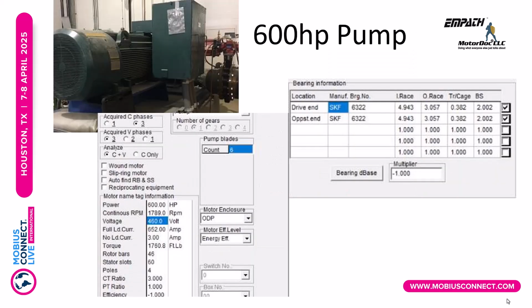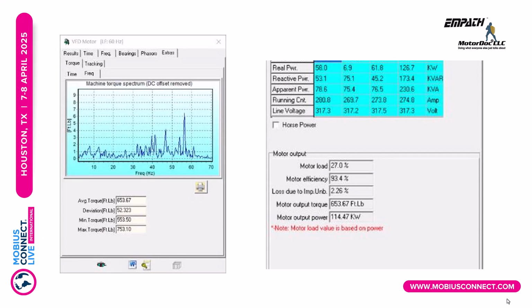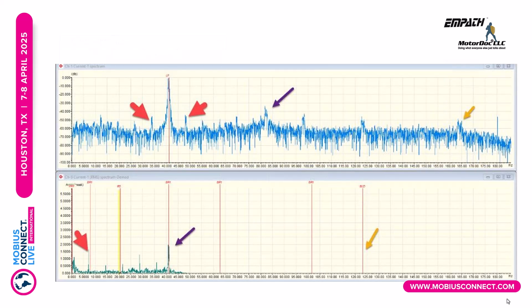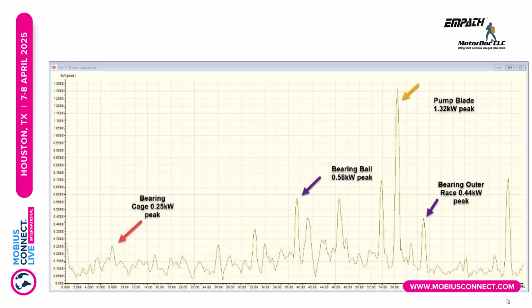This one here, 300 horsepower machine, we're going to drop that one. 600 horsepower machine, this is the one where they put in the shims. They used one shim pack across 3 machines and spaced it up at least an inch. In this case, you can see that there's bearing stuff there. When we take a look, there were also things including static eccentricity, because when they torqued down on those bolts, they caused the stator to warp a little bit.